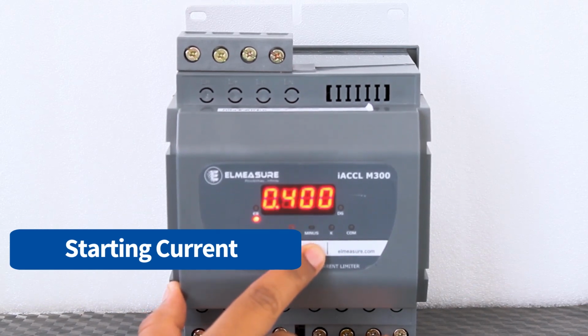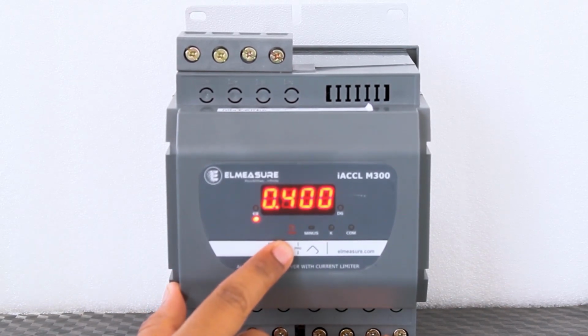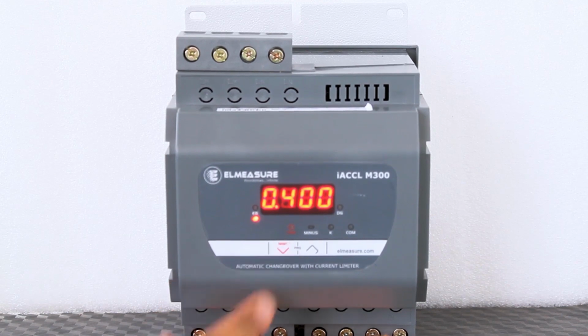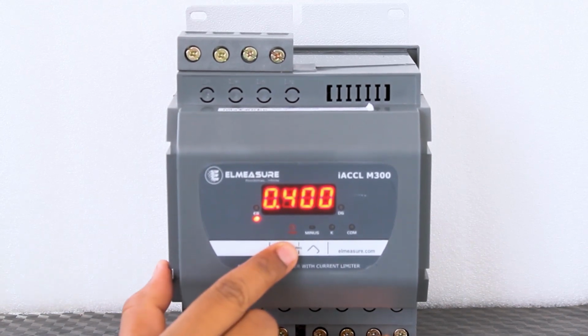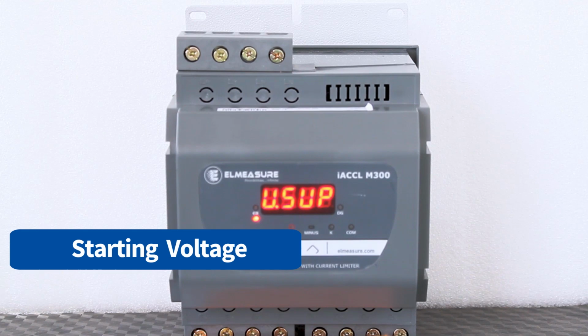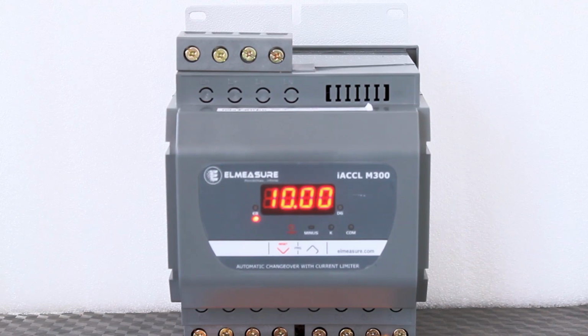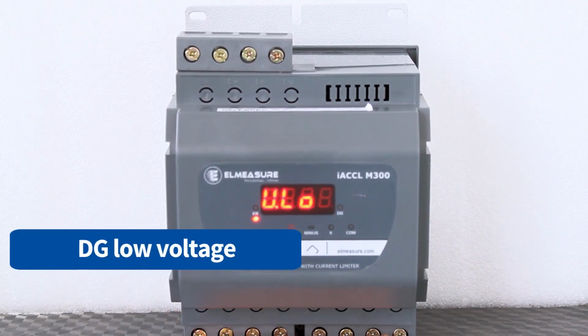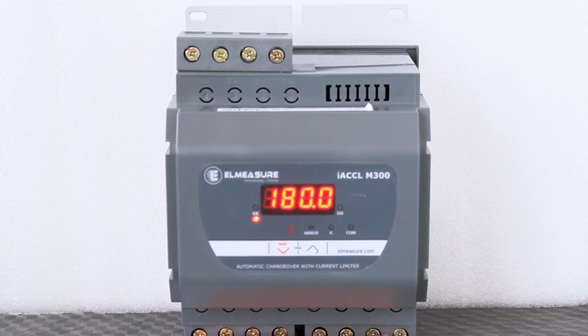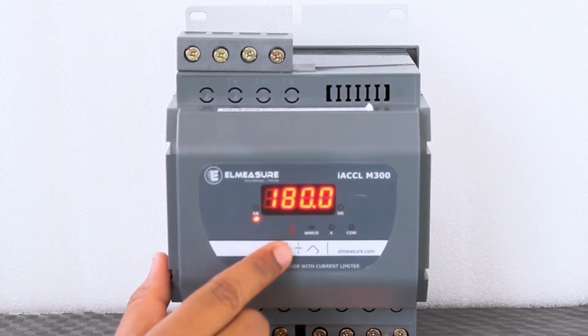This is starting amps. By default the value will be 0.4, but we can set the range from 0.2 to 10% full scale. This is starting voltage. By default the value will be 10. You can set the range from 10 to 40 volt. This is DG low voltage. By default it will be 180. You can set the range from 165 to 210 volt.